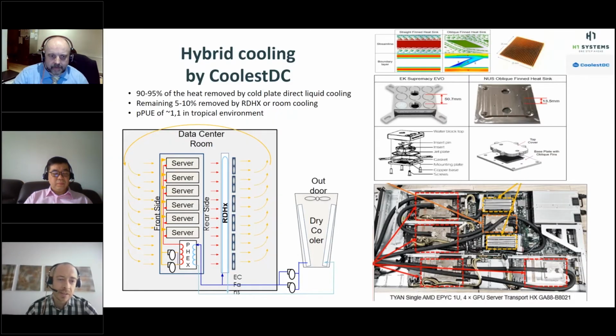I'm very proud to have closely seen the testing of a new Singapore startup, Coolest DC, which is a hybrid cooling technology. If you compare this to what's pretty common now in data centers, the inefficiency gap - the actual cost gap between the two - is huge. Adopting this liquid cooling solution actually costs the same as an air-cooled solution, but the required footprint is one-fifth for the same computing capacity compared to air cooling solutions.